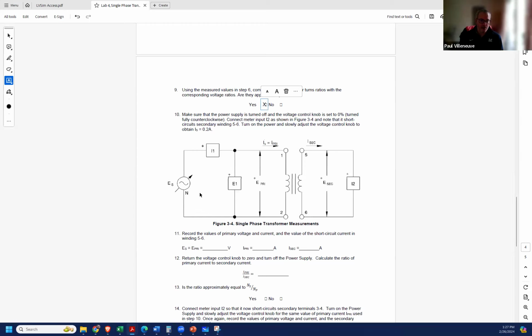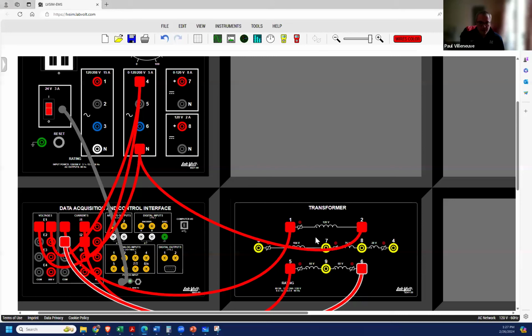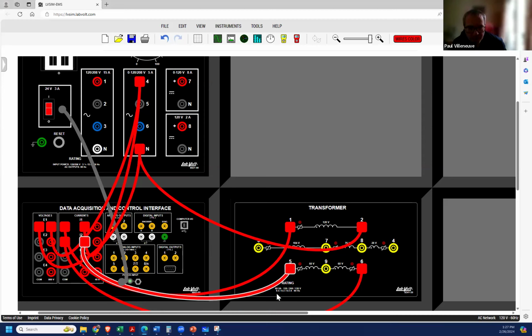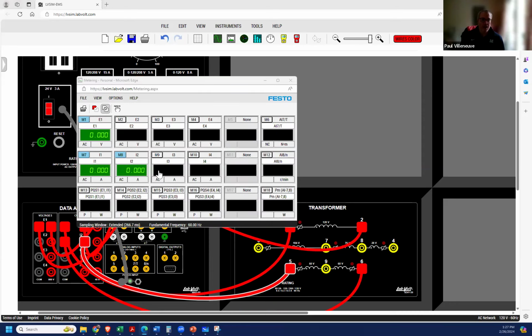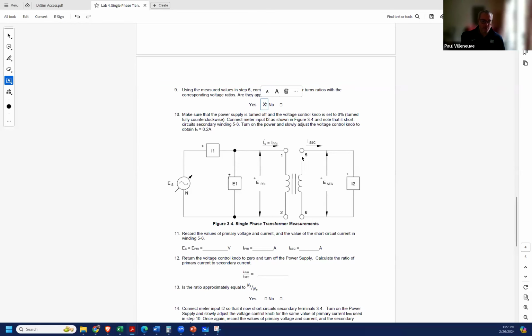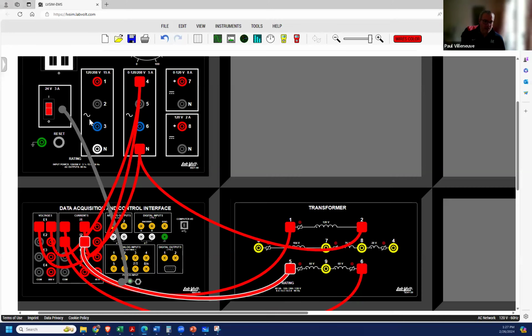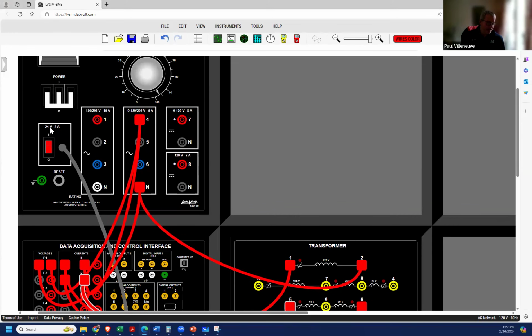So here's what we need to do. We need to make sure that we don't overdrive this transformer by putting too much current in it, because if you look at the nameplate of the transformer, it says, depending on the winding, you can do 0.5, 0.3, or 0.5. So what we're going to do is limit it even less, and only drive 0.2 amps through this device. And when I turn this up, I have to turn that up incredibly slowly. So let's turn it all the way down so I don't trip the transformer. So I'm going to have to turn this up very slowly while monitoring my current.